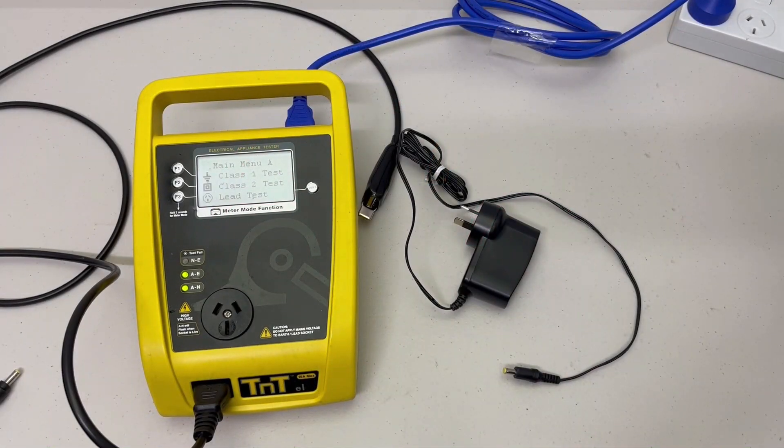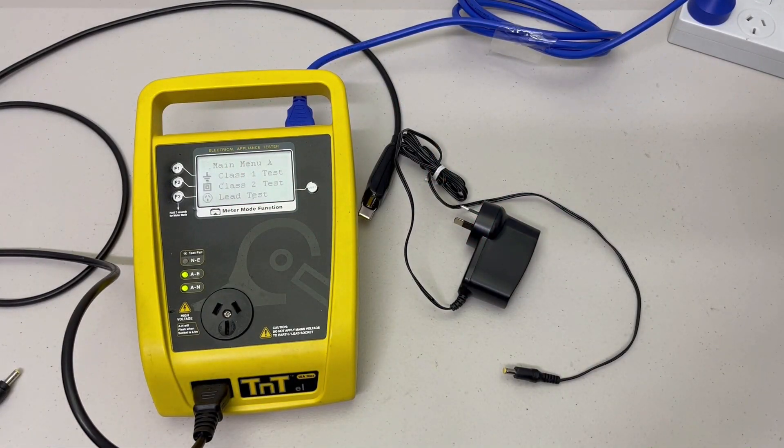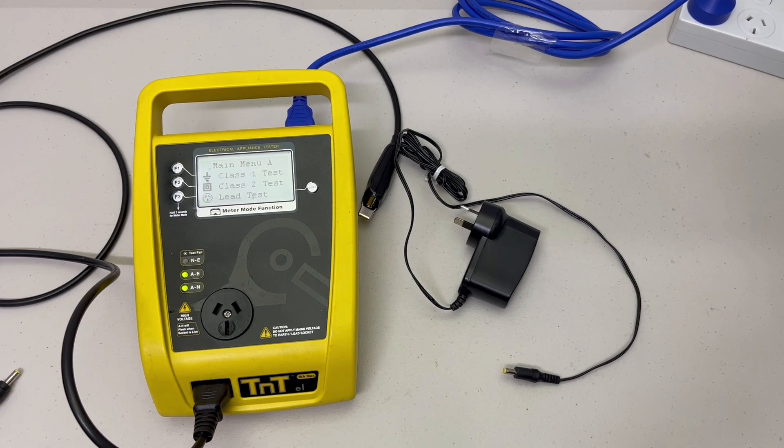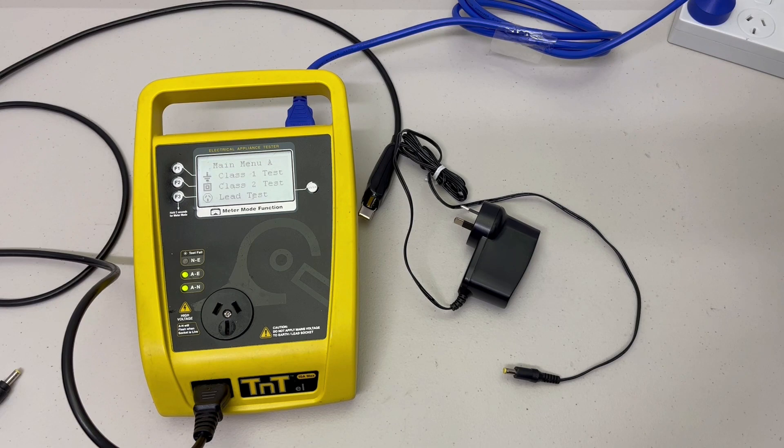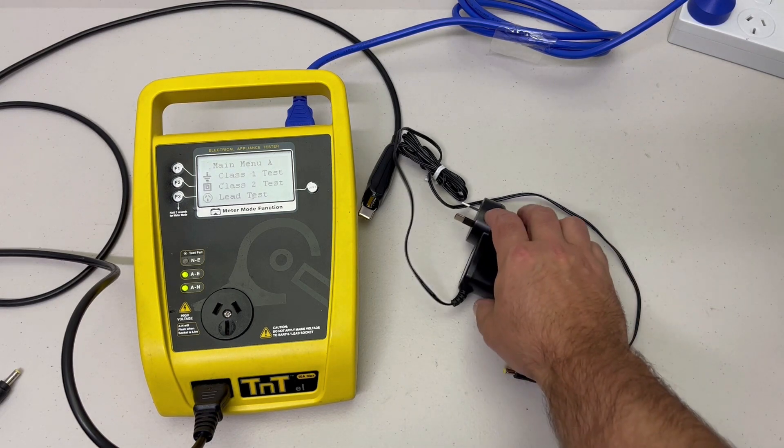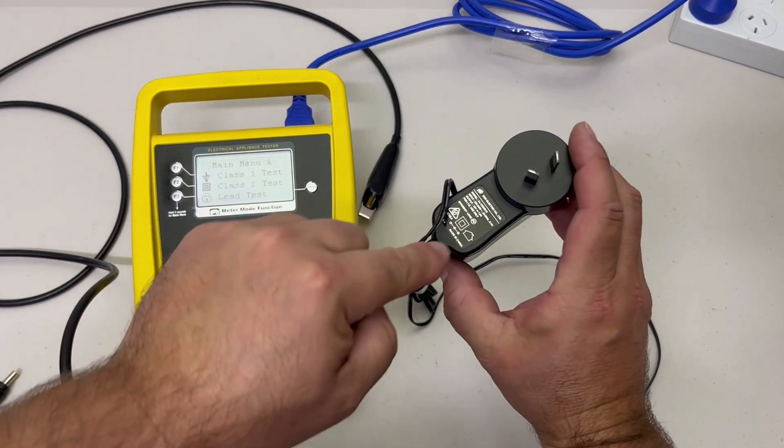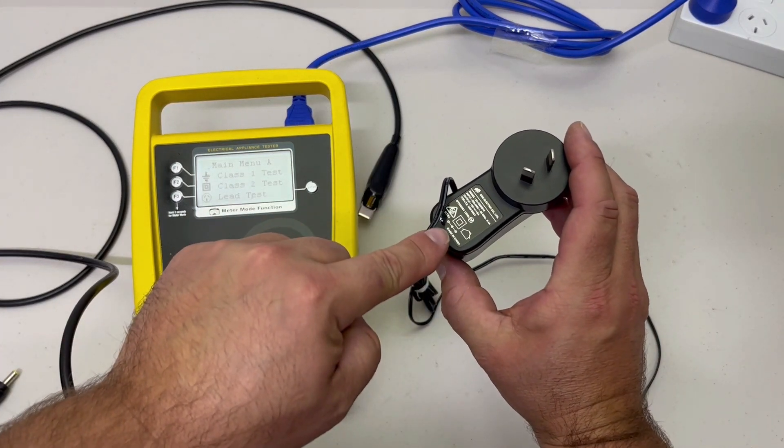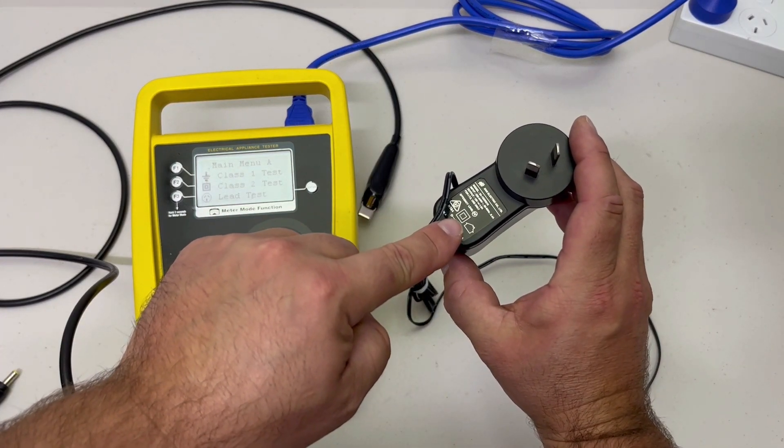In this video we're going to test a DC power supply. We have already completed a visual inspection on this appliance. The compliance label has the double insulated symbol, so therefore it is a class 2 appliance.